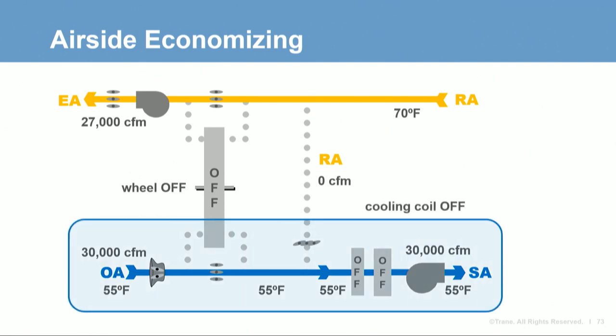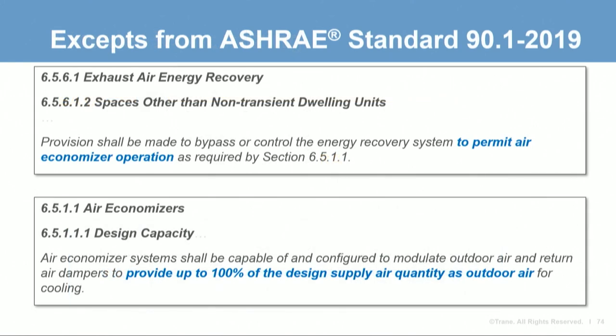If this system includes air-side economizing capability, it would likely be in economizing mode at mild conditions — the outdoor damper is fully open, the recirculating damper is closed, and all 30,000 CFM of supply air comes from outdoors with no mechanical cooling required. To accommodate economizer operation, bypass dampers are added to allow full economizer airflow without significantly increasing the air-side pressure drop and fan energy. This is part of the ASHRAE 90.1 requirements: if an economizer is required, the energy recovery system must include some provision to permit economizer operation.